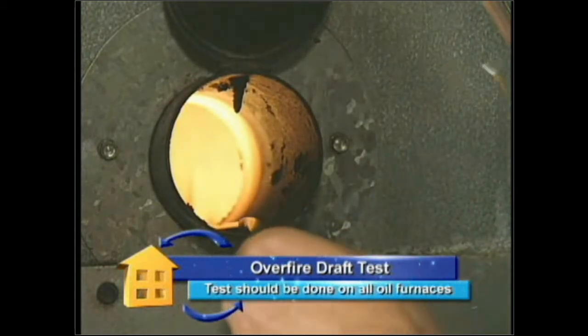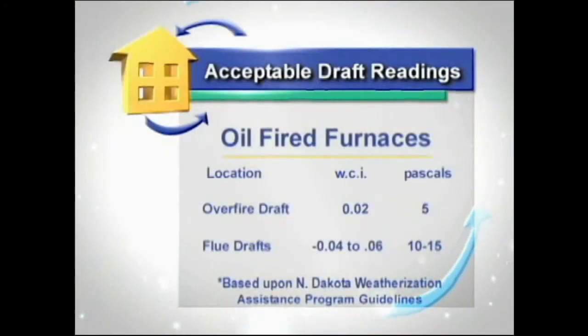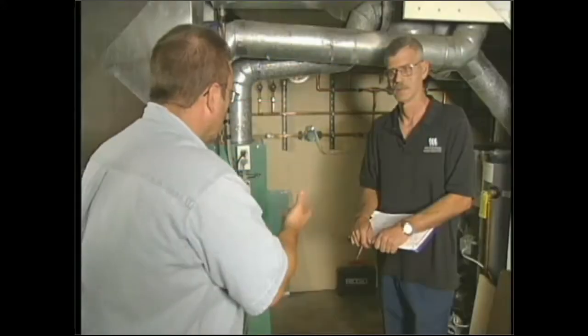So we don't want it to misshape that flame or cause impingement. Okay? And what ideally we want is 0.02 inches of water column or 5 pascals measured over the fire. So this seems to me to be a very important test because you want to ensure that that draft is not misshaping that flame. It's keeping it nice and straight and not swaying it from one side to the other? Yes, because once it starts to go to one side or the other, if it strikes the side of the burning chamber or the fire pot, it can start to create soot and other concerns.